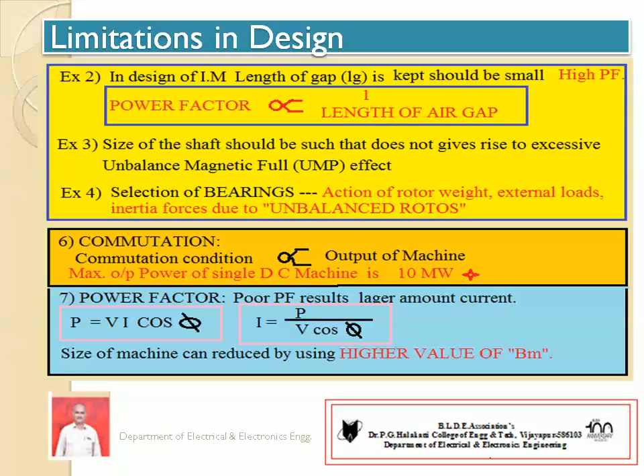Very important, power factor. If we have a lower power factor, then the machine will draw more current. The size of the machine can be reduced by using a higher value of flux density. But if I use a higher value of flux density, then it results in poor power factor. It is slightly confusing. A higher value of flux density is required to increase the capacity or rating of the machine. On the other hand, if we select a higher value of flux density, then power factor is low. Hence, keep these two points in mind when selecting flux density, for a moderate power factor and the output of the machine. Power factor also depends on length of air gap, as in the previous point.